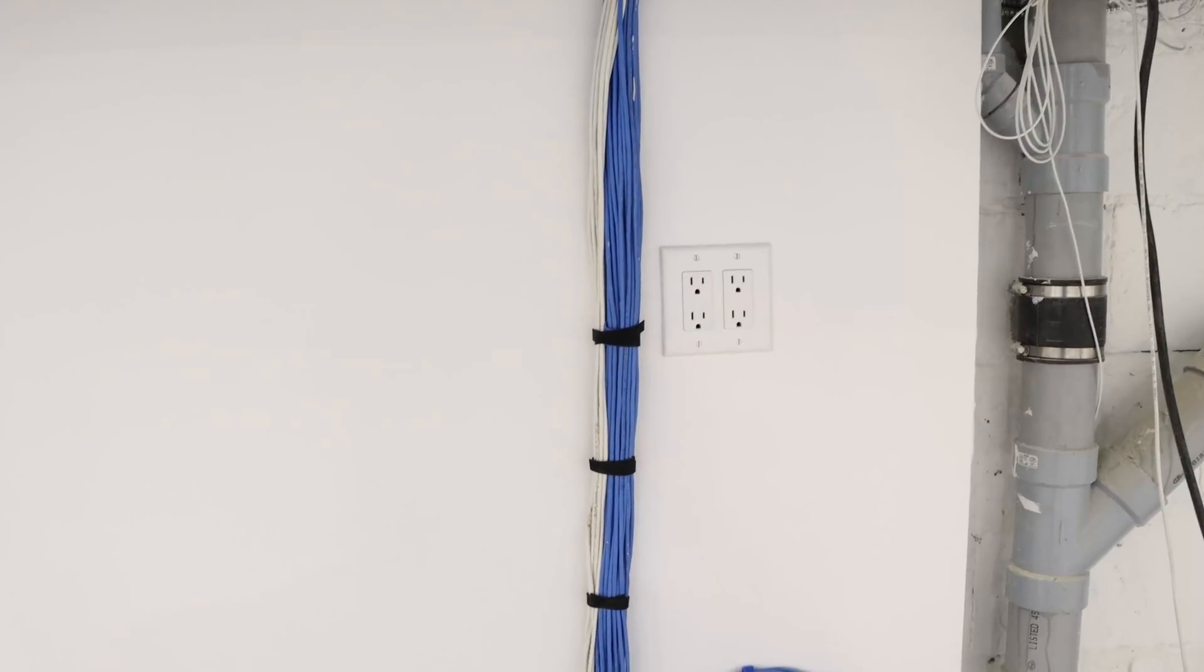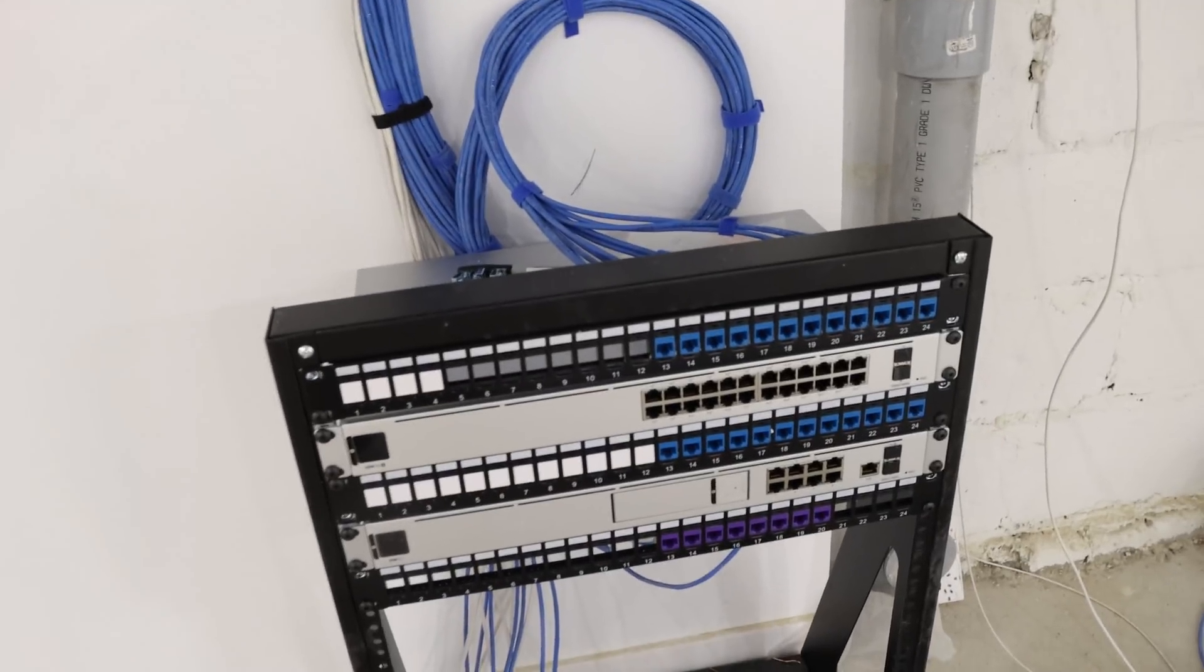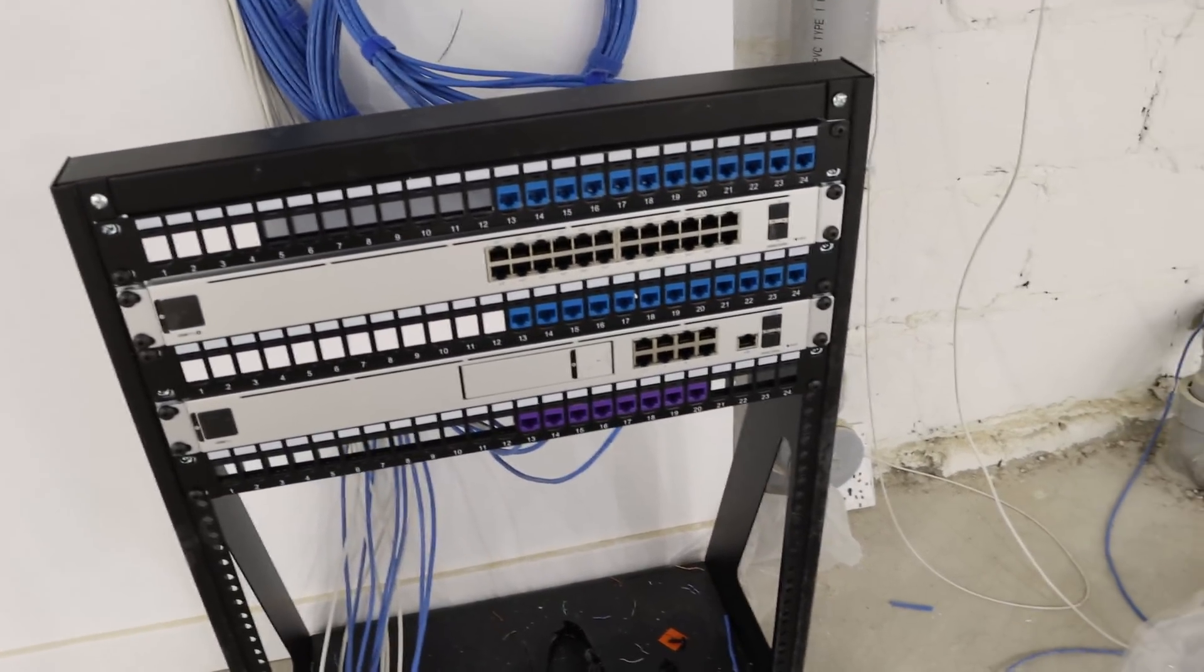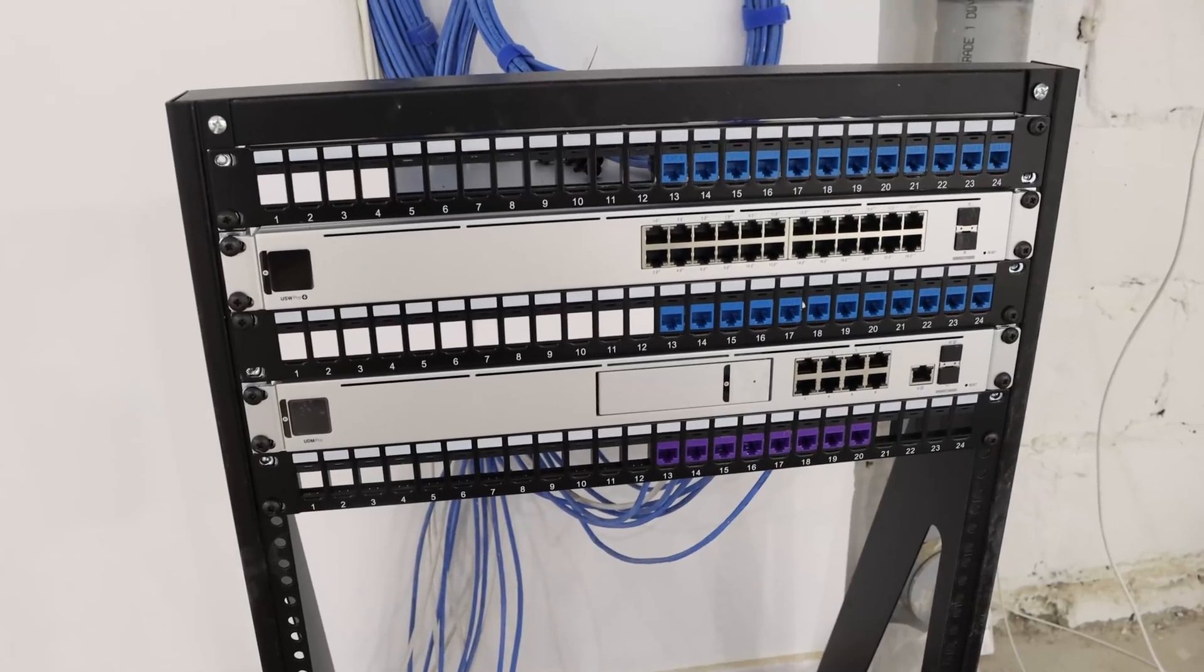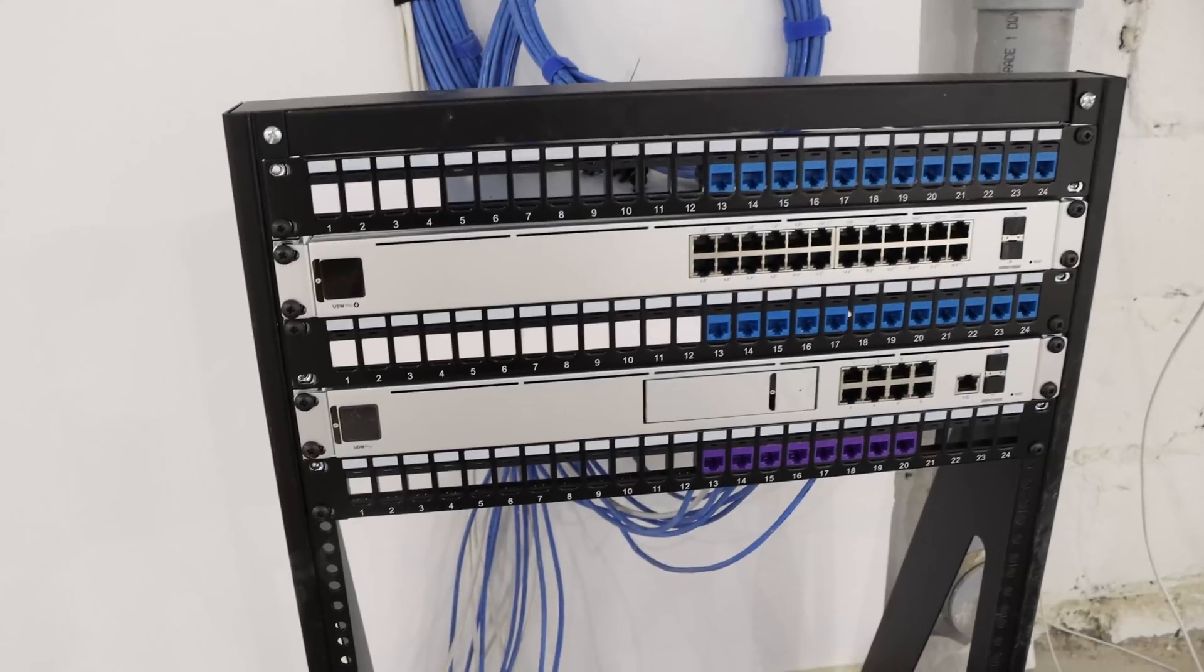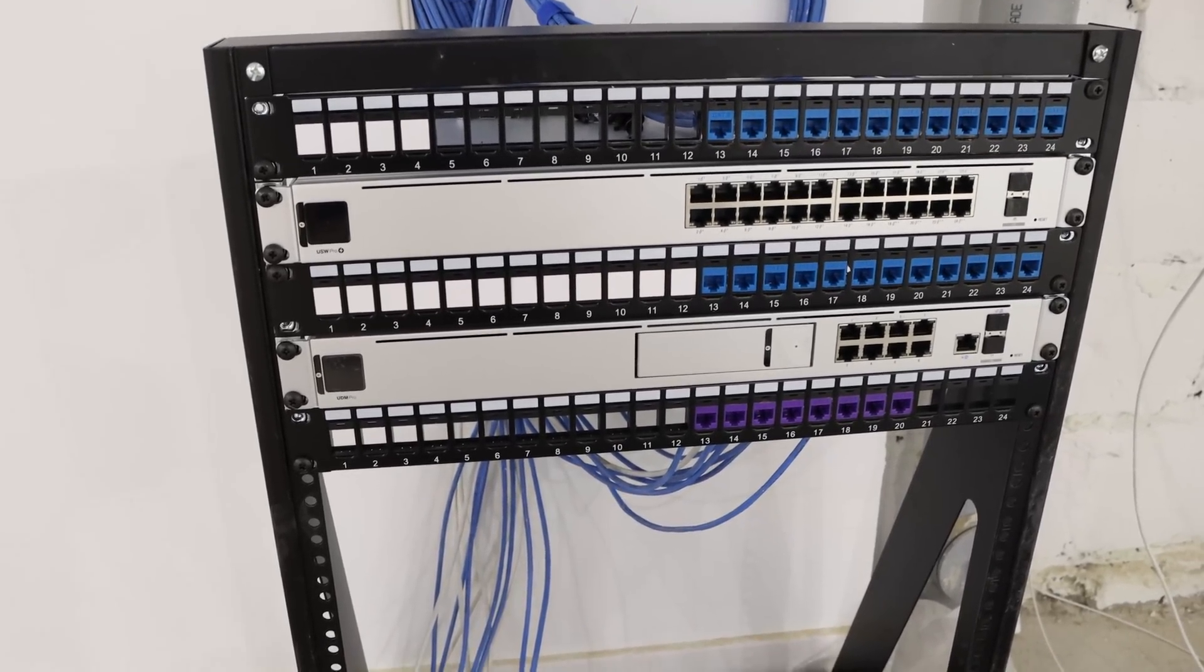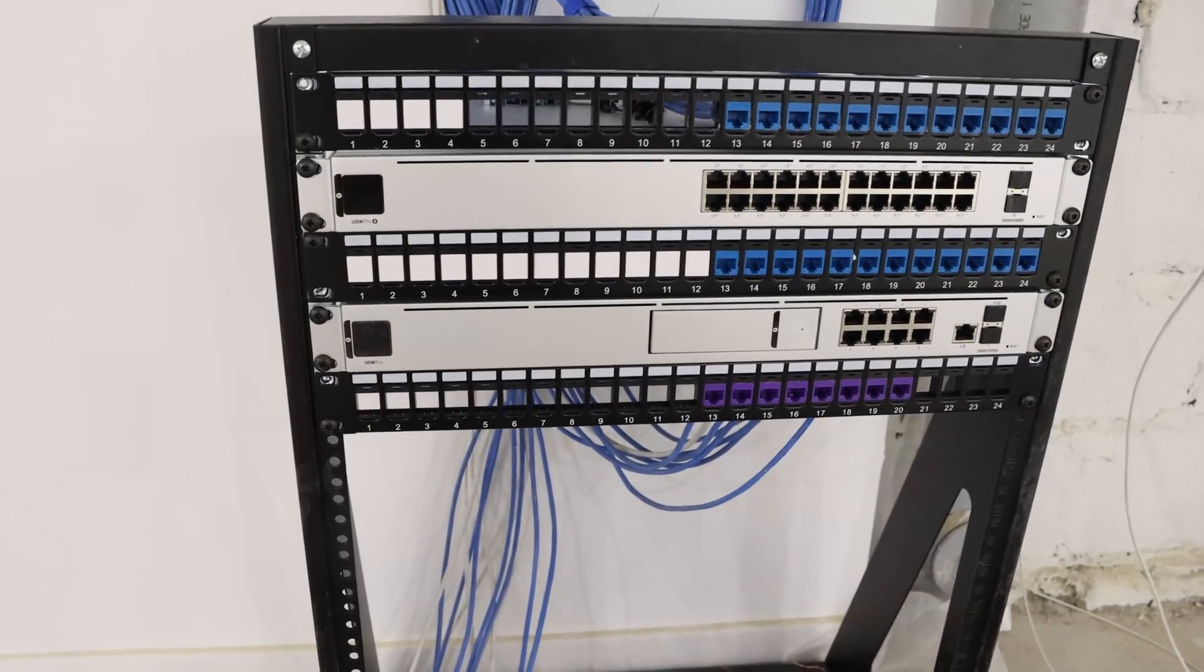So I bundled the rest of the cables down with the original data cables. If we look down we have our 12 data cables on top and then a 24-port USW Pro switch. And then below that we have another 12 ports. I already installed the UDM Pro and then 8 camera cables. So the cameras are going to be on these purple keystones. The access points we're going to put on yellow keystones and then we have a few more data jacks. Below this patch panel we'll be putting in another USW24 PoE and then another patch panel and we have a UNVR and a battery backup to go on the bottom. So now we need to finish terminating.